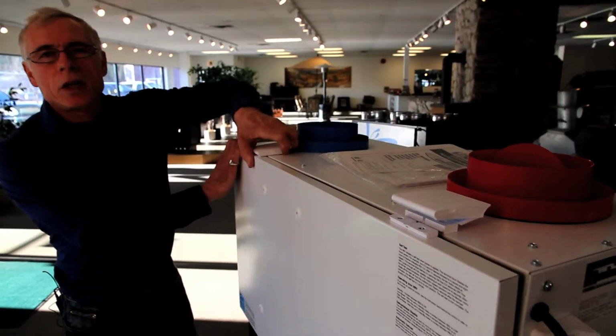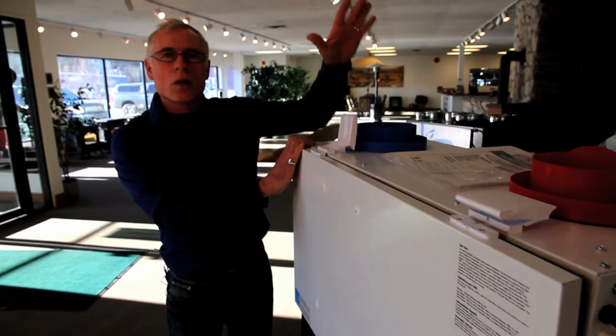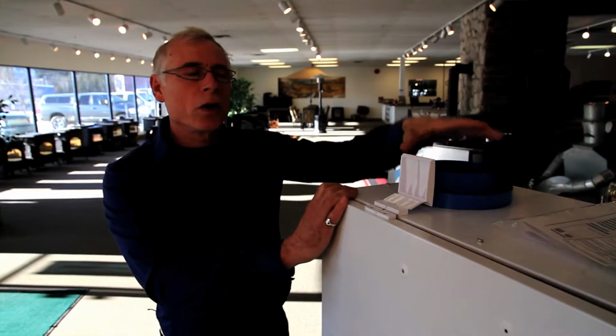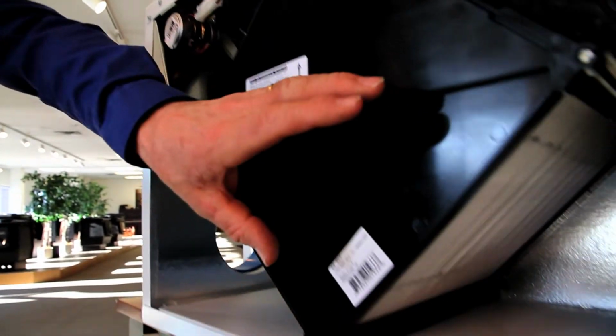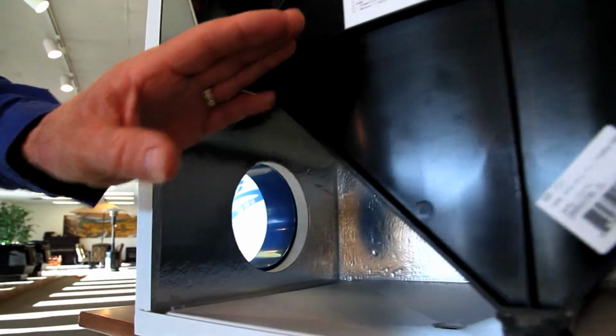Now let's take a look at an HRV and see how they operate. We have basically two air streams in an HRV, your exterior fresh air and your warm interior air. So in this case, the fresh exterior air comes in here, it goes in an airstream through the heat exchanger, through here, and puts fresh air into your house. The second airstream is your exhaust from your bathroom and your kitchen that brings a warmer airstream through these channels in the heat exchanger and dumps the heat, but not mixing the air, and exhausts it outside the house.